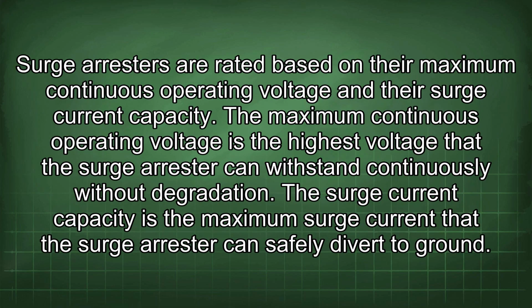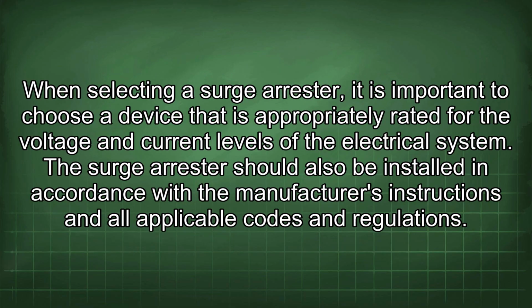Surge arresters are rated based on their maximum continuous operating voltage and their surge current capacity. The maximum continuous operating voltage is the highest voltage that the surge arrestor can withstand continuously without degradation. The surge current capacity is the maximum surge current that the surge arrestor can safely divert to ground. When selecting a surge arrestor, it is important to choose a device that is appropriately rated for the voltage and current levels of the electrical system. The surge arrestor should also be installed in accordance with the manufacturer's instructions and all applicable codes and regulations.